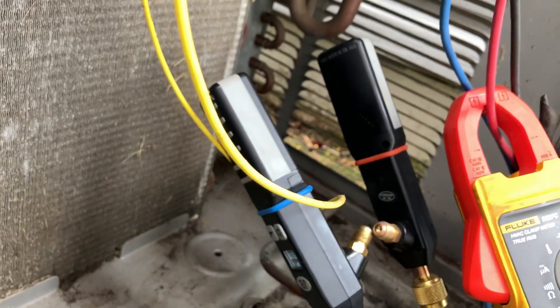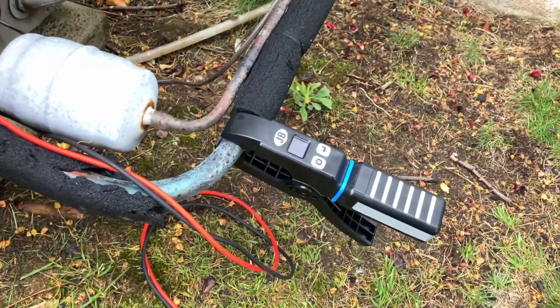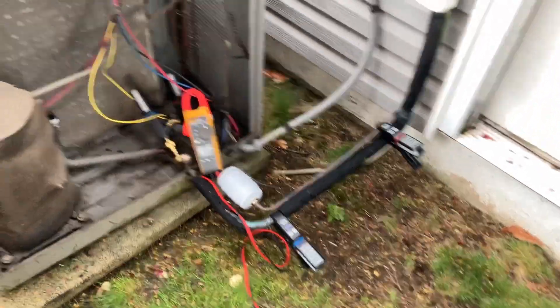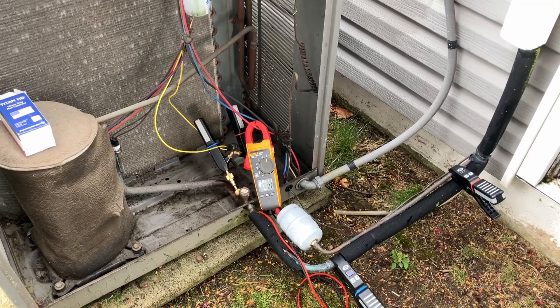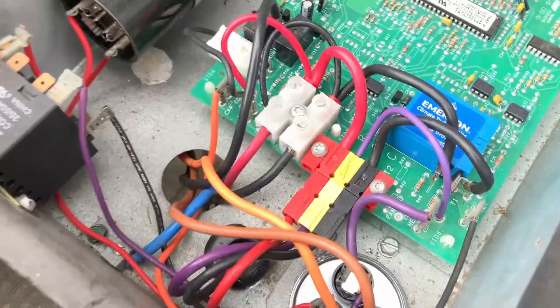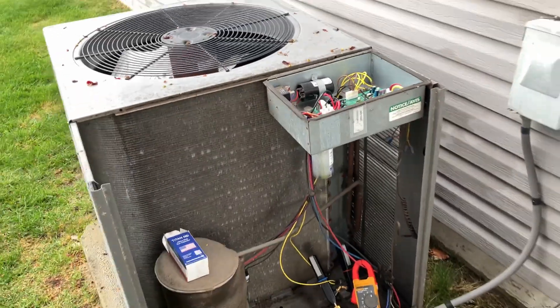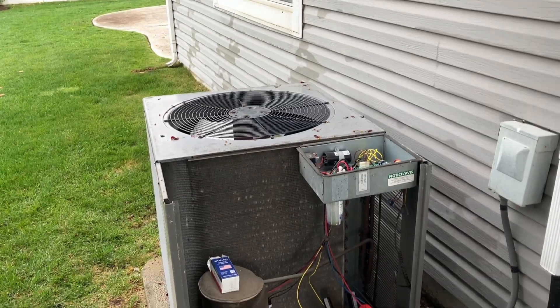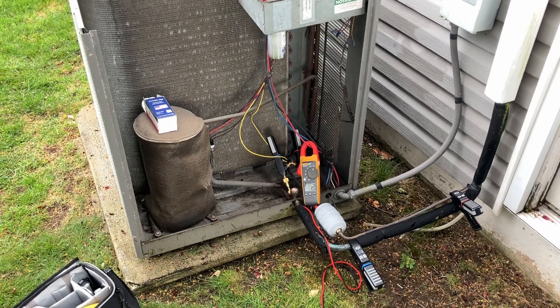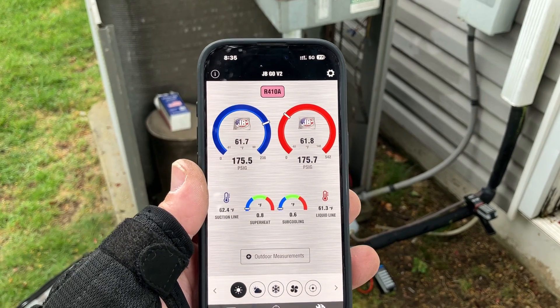I've got my JB Just Better Climate Class smart probes connected to the suction, liquid, and clamp-on temperature probes on both suction and liquid lines. My Fluke 902 FC clamp-on amp meter is on L1 or L2, one of the lines of voltage coming in. We're waiting for that little LED to stop flashing — once it stops, we'll have the compressor turn on, a condenser fan motor, and we'll watch the startup amperage. I've got the JB Go version 2.0 app in standby mode waiting for it to kick on.